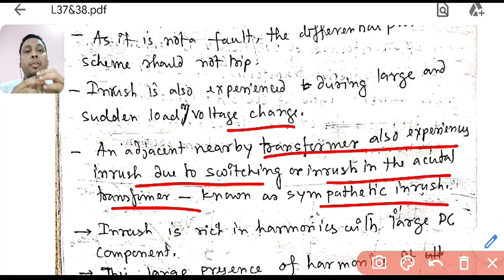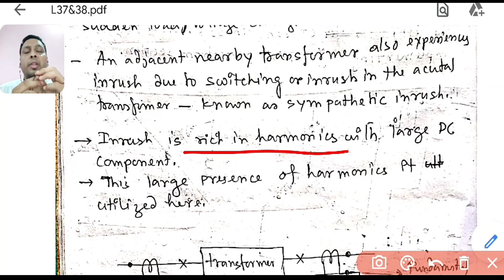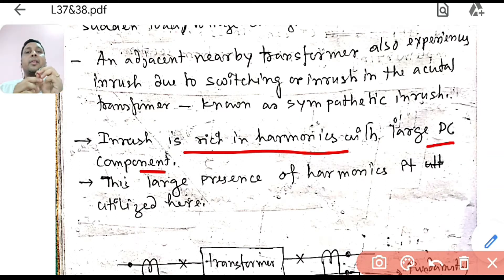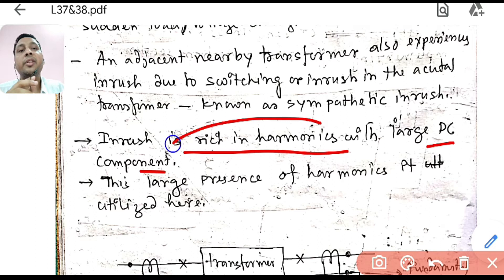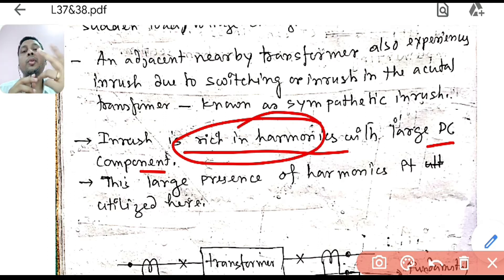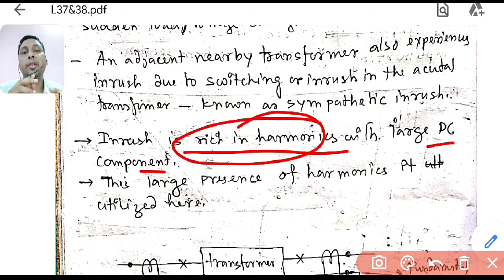The inrush current is very rich in harmonics, with very high harmonic contents along with large DC components. This makes it different from a normal fault current, where harmonics are not so high. This difference between normal current and inrush current can be utilized so the relay can sense which one is a fault and which one is inrush — that is why it is known as harmonic restraint.